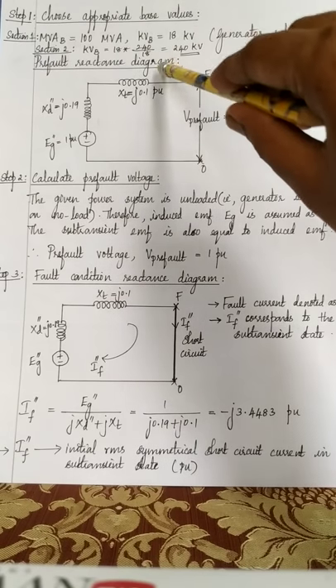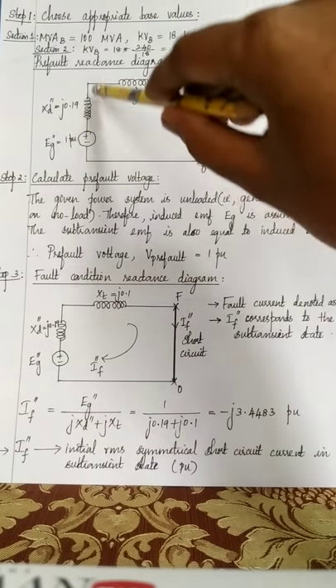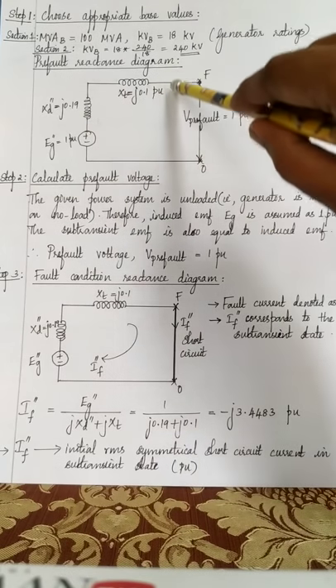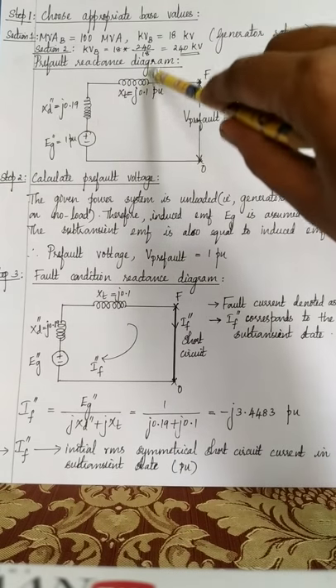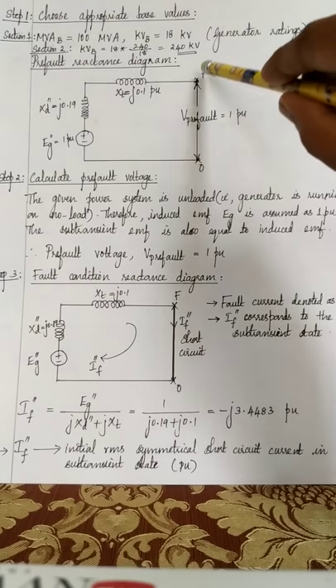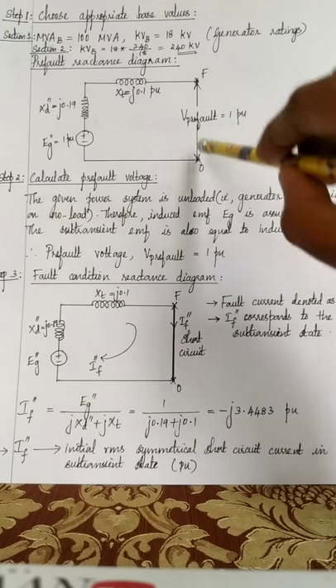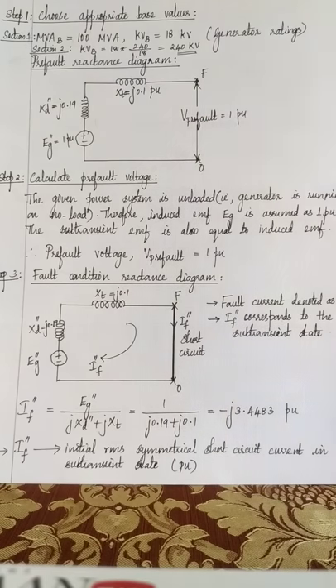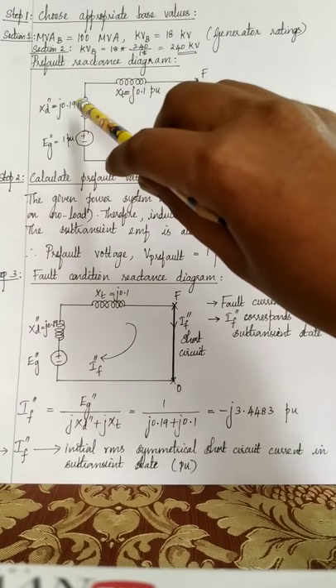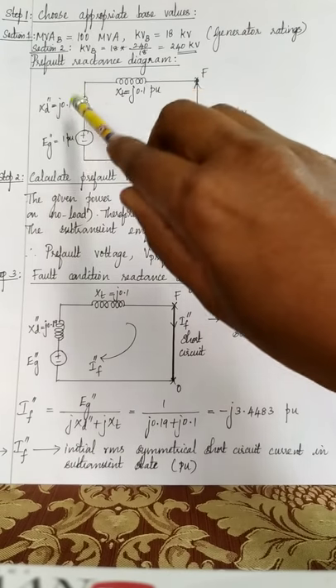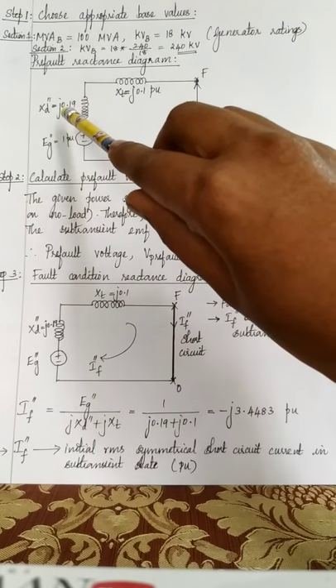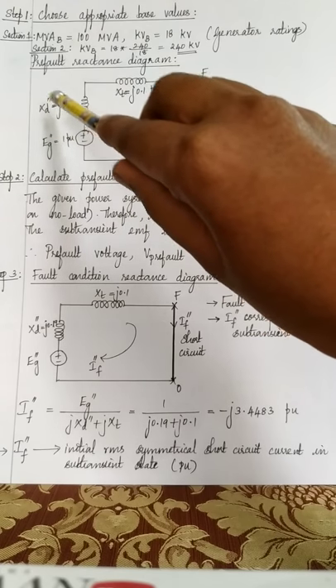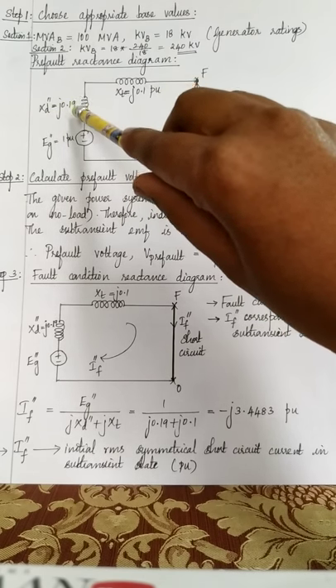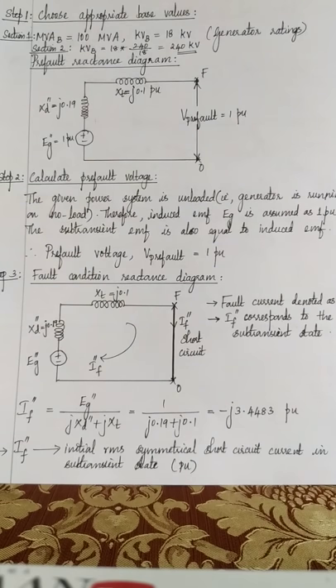So now draw the pre-fault reactance diagram. We have the generator and the transformer. At the high tension side of the transformer, the fault occurs, so the fault terminals are F and O. And mark the pre-fault voltage. Now, since the generator ratings are taken as the common base, there will not be any change in XD double dash, which is j0.19. Old value and the new value will be the same.